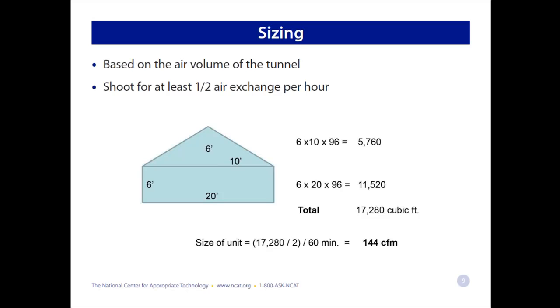This would mean that every 2 hours, the entire volume of air in the high tunnel would be exchanged with fresh air. And I felt that that would be good enough to try to get most of the humidity out of one of these tunnels. So in order to get that number, I divided the total air volume by two, and then divided that number by 60 minutes. And that ended up being 144 cubic feet per minute is the size unit that I would have needed.